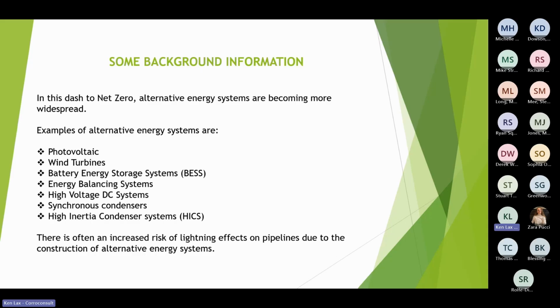But they all do provide an increased risk to the pipeline, which at the time of design and construction is often not quantified. And there's also the hidden risk that if you have a pipeline minding its own business buried in a rural area, the pipeline risk from lightning strikes would have been evaluated and considered to be pretty low. Unfortunately, some of these systems, especially wind turbines, do increase the risk of lightning strike on the buried pipeline. And as we'll explain to you a bit later on, a lightning strike is a massive wallop of current into the soil, and it disperses through the soil and does affect the pipeline even at quite significant distances. So we do really need to keep those in mind as well.